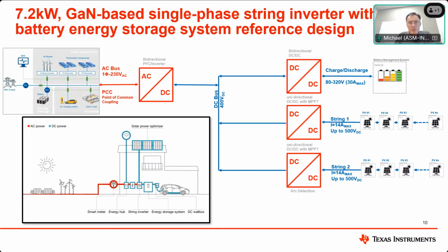In residential use, very often 400-watt PV panels are used. The typical maximum power point voltage of such panels is in the range of 33 volts, meaning if 10 PV panels are connected, the voltage present on a string input would be around 330 volts. 10 panels would also mean the power available at each input can be as high as 4 kilowatts. For 2 string inputs, we are at 8 kilowatts.